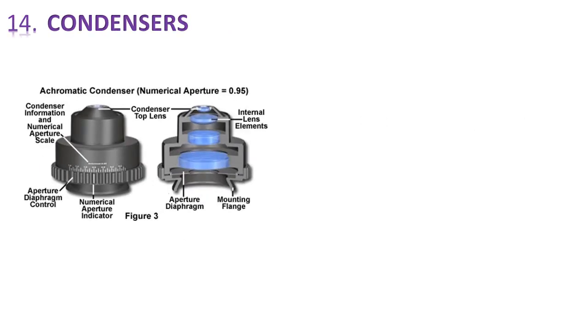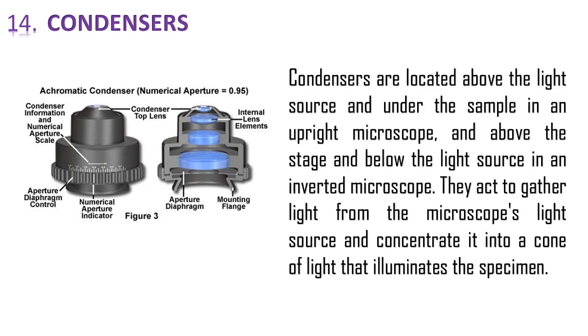And the 14th one is condensers. Condensers are available in different numerical apertures. They are a lens system which focuses the light to concentrate it into a cone of light that illuminates the specimen. Condensers are located above the light source and under the sample in an upright microscope, and above the stage and below the light source in an inverted microscope.